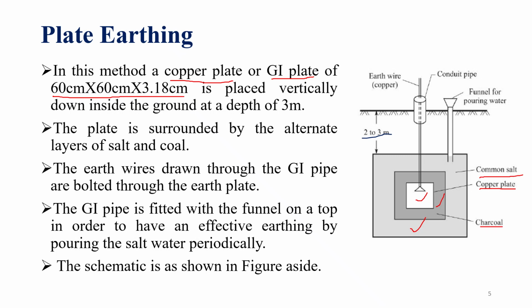So this is the copper plate, white color, and this light dark color is charcoal, and the outer layer is common salt. The earthwire is above the ground level, and we have dug a pit around 2 to 3 meters and placed in the copper plate. In order to join this, we are going to use a GI pipe. Through the GI pipe, the earthwire is passed onto the earth plate. At the earth plate, it is connected by using some bolts, and there will be a funnel arrangement. Through that funnel, in order to increase the effectiveness of the earthing, we are going to pour salt water periodically.